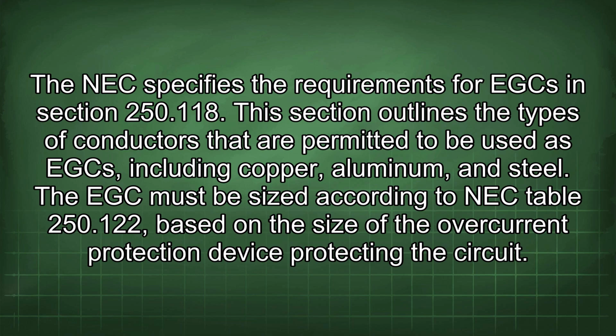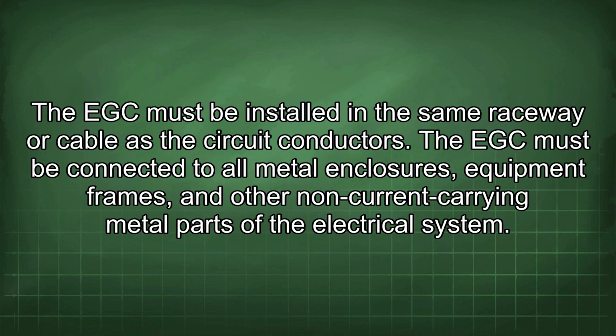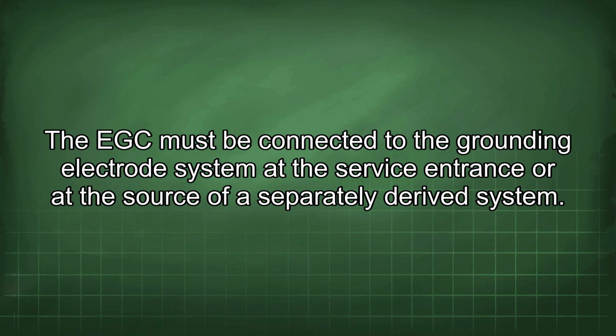250.118. This section outlines the types of conductors that are permitted to be used as EGC, including copper, aluminum, and steel. The EGC must be sized according to NEC Table 250.122, based on the size of the overcurrent protection device protecting the circuit. The EGC must be installed in the same raceway or cable as the circuit conductors. The EGC must be connected to all metal enclosures, equipment frames, and other non-current carrying metal parts of the electrical system.